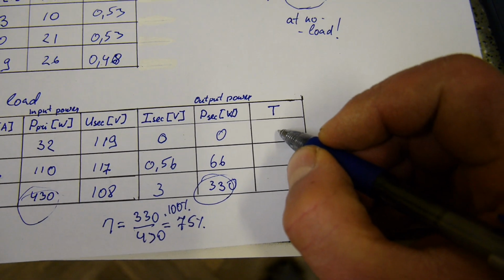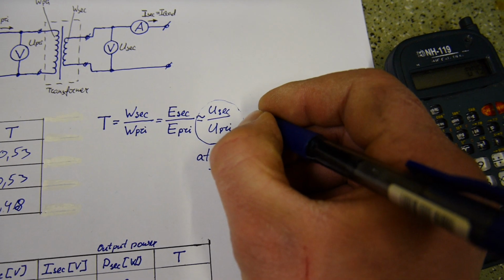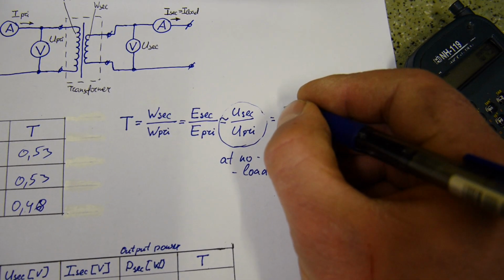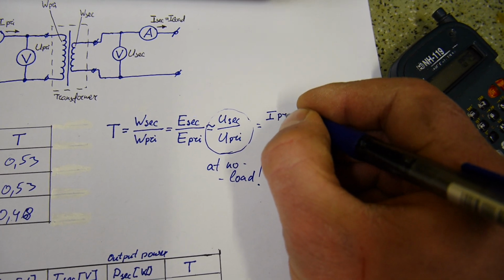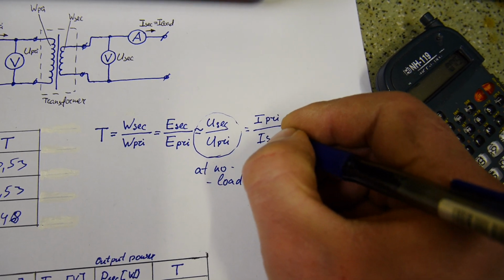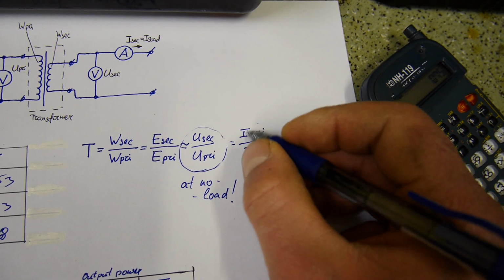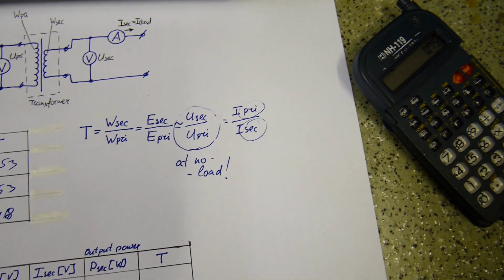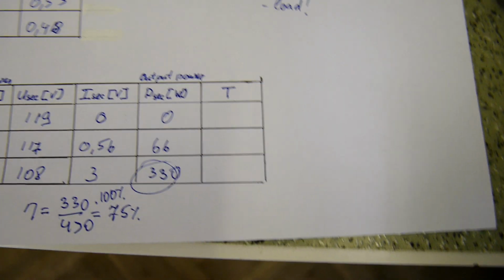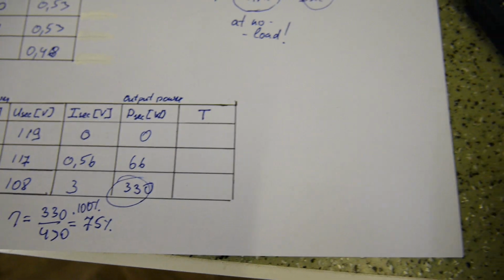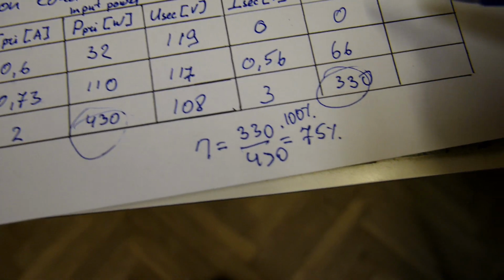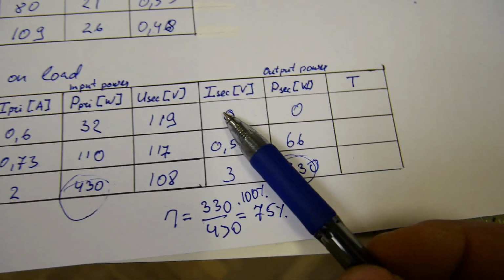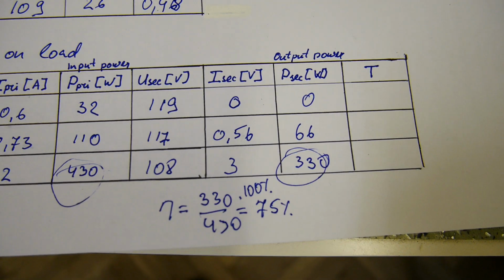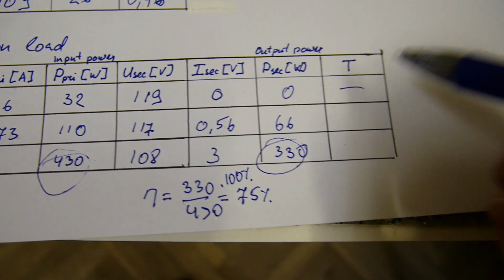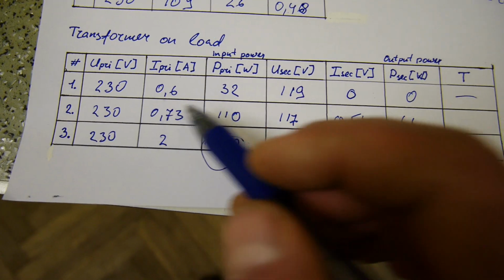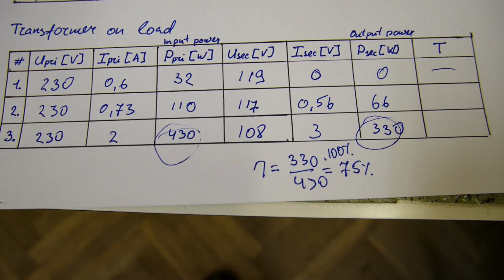Also, we can calculate turn ratio by means of currents, but in this case you have to divide primary current by the secondary current. So these two are reversed, yeah, swapped. So again, primary by secondary. Primary by 0 gives us infinitely high value. So we can't do this. Primary by secondary, here we can calculate, yeah.